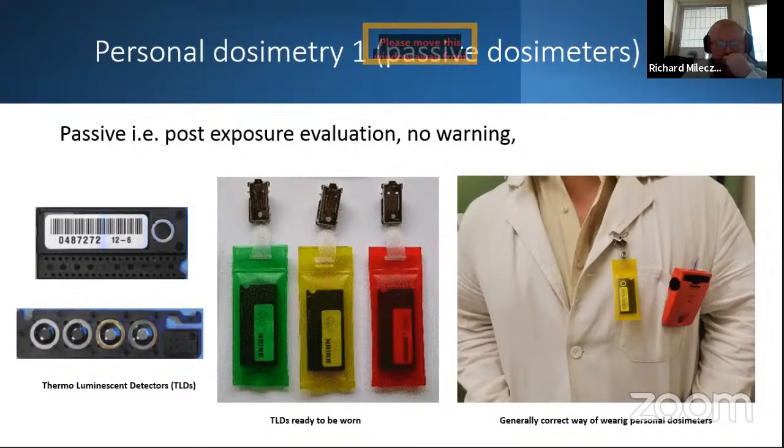You can take the crystals and the shielding themselves and encase them, forming a single unit. Then you can wear this single unit on yourself. This is usually done when you are trying to measure whole body doses. When you are trying to measure a certain body part, or rather exposure of the body part, then you can take a single crystal or a more complicated unit and attach it to a ring or glasses.